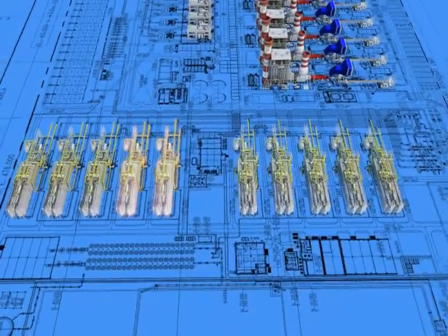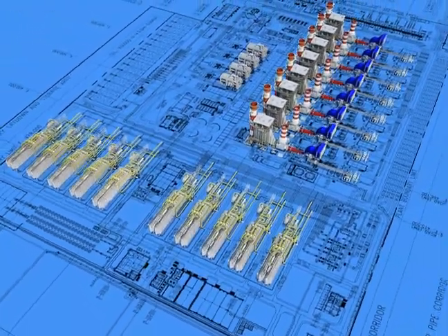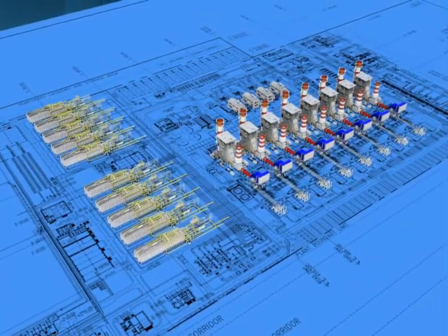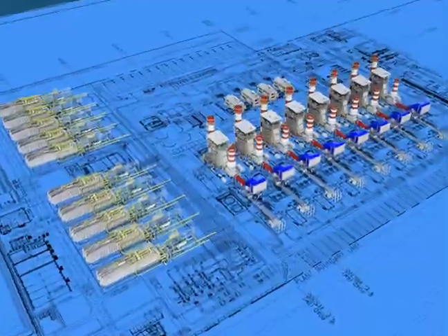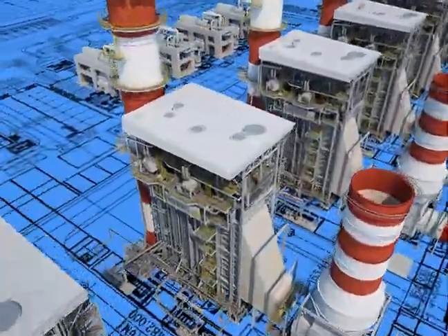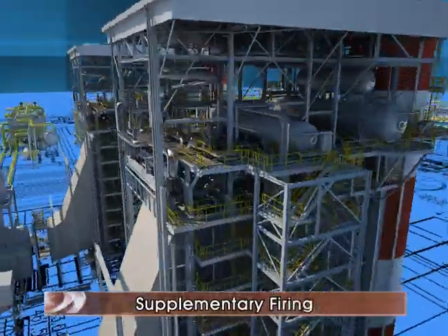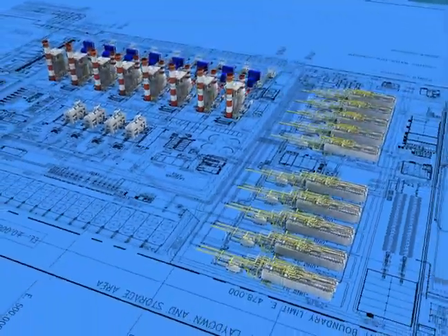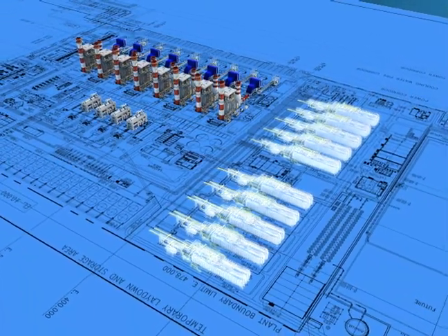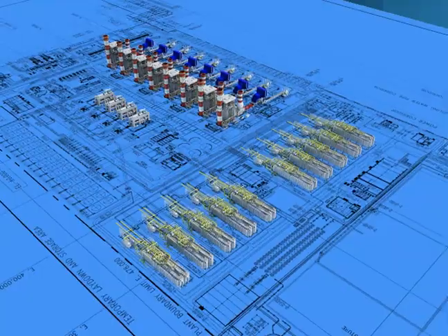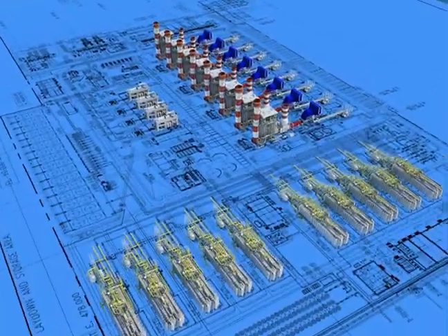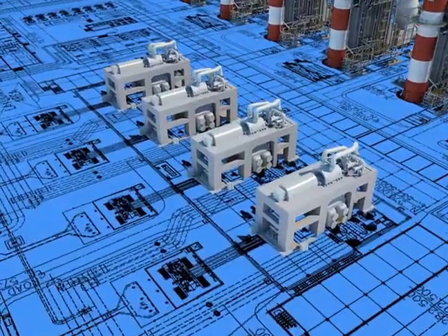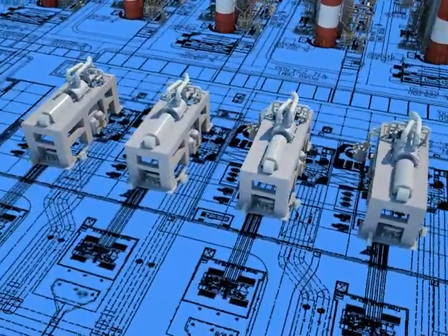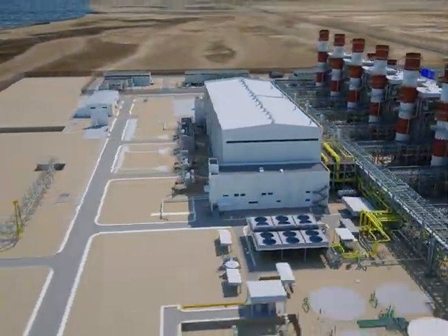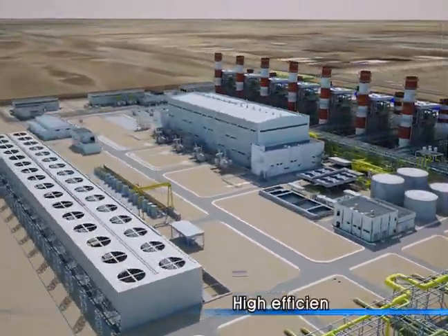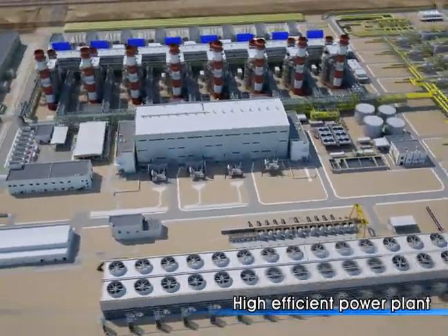The stability of power and water production was maximized to satisfy the power and water demands for each season. Each HRSG has supplementary firing facilities. The plant is designed so 2 HRSGs alone can supply the steam required for the 10 MED units. Despite the different amount of extraction steam, the steam turbine generators of each block were designed to equally maintain maximum production output. The water processing facilities and plant cooling facilities are joint facilities to make the plant more economic.